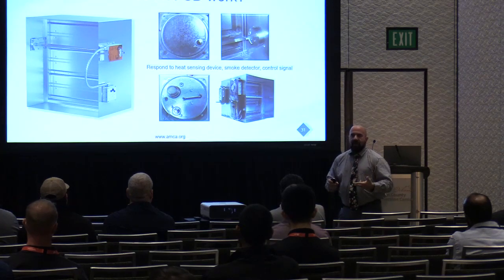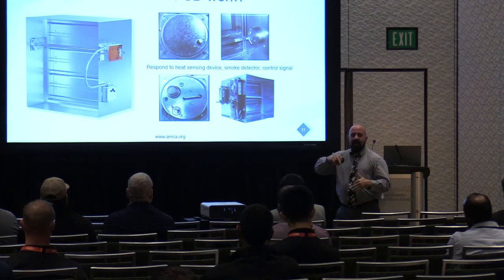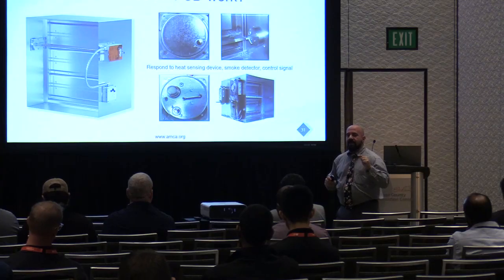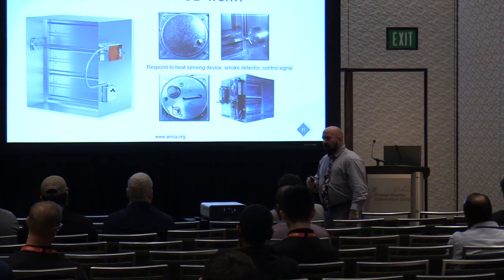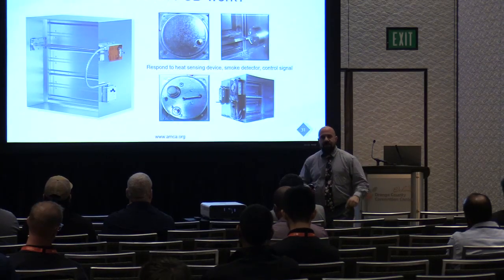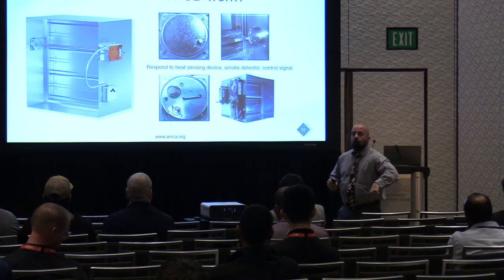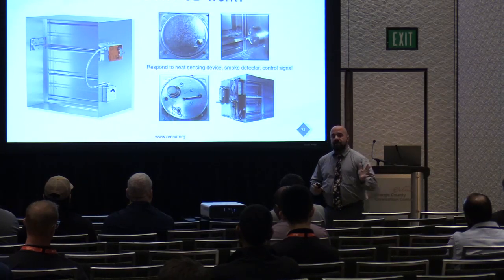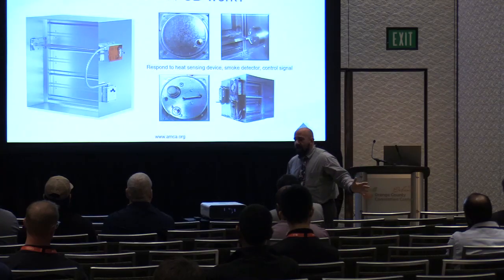Building will report a fire, the dampers will close. I have the ability to reopen that damper from my fire alarm control panel, building management system, somewhere. I can push a button, reopen that damper so I can use it for smoke control. Once that fire gets more intense and that high limit is reached, the damper automatically closes again and becomes part of that wall, makes up that containment, that compartmentalization of the barrier.